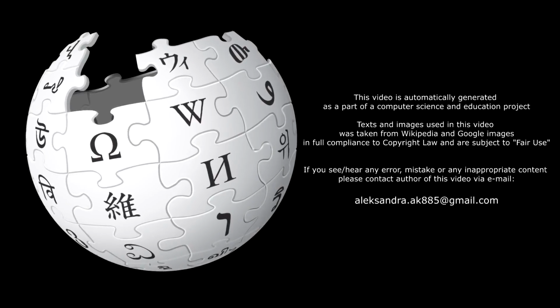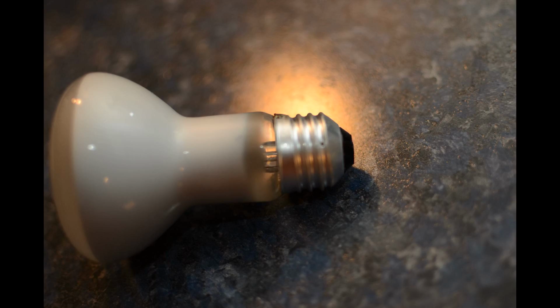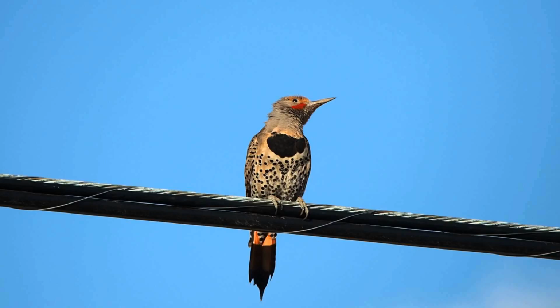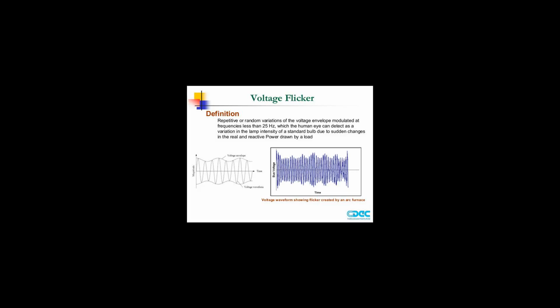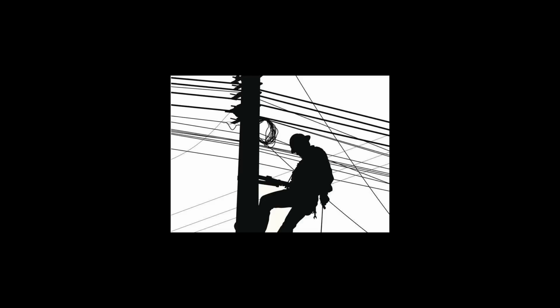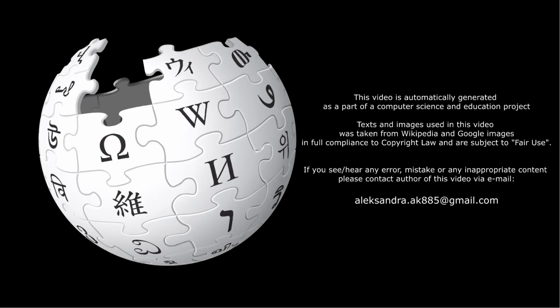Power line flicker is a visible change in brightness of a lamp due to rapid fluctuations in the voltage of the power supply. The voltage drop is generated over the source impedance of the grid by the changing load current of an equipment or facility. These fluctuations in time generate flicker. The effects can range from disturbance to epileptic attacks of photosensitive persons. Flicker may also affect sensitive electronic equipment such as television receivers or industrial processes relying on constant electrical power.